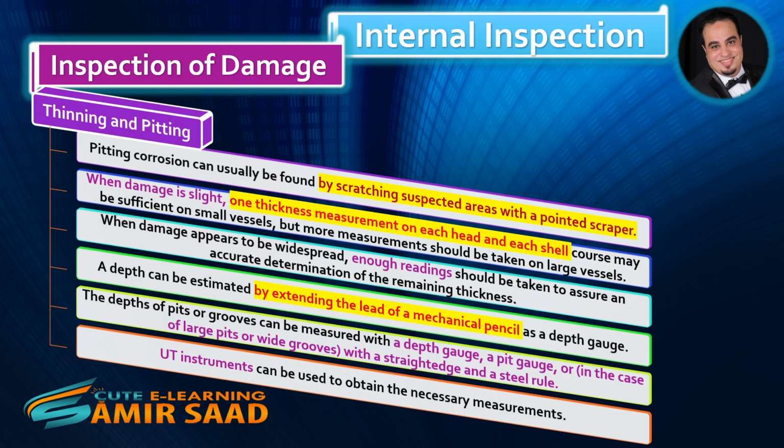A depth can be estimated by extending the lead of a mechanical pencil as a depth gauge. The depths of pits or grooves can be measured with a depth gauge, a pit gauge, or, in the case of large pits or wide grooves, with a straightedge and a steel rule. UT instruments can be used to obtain the necessary measurements.